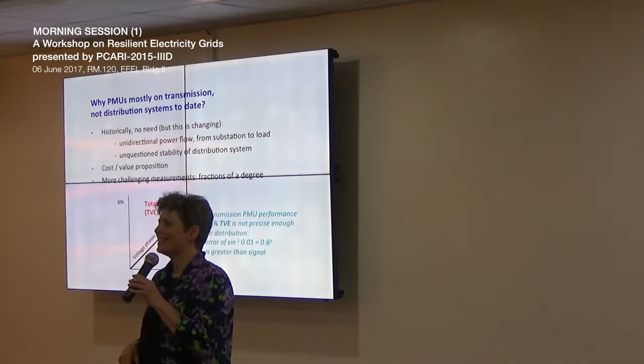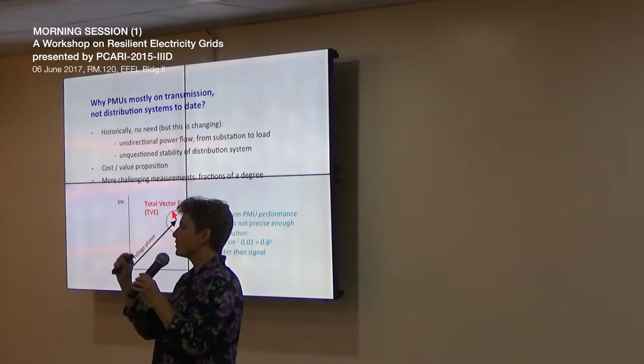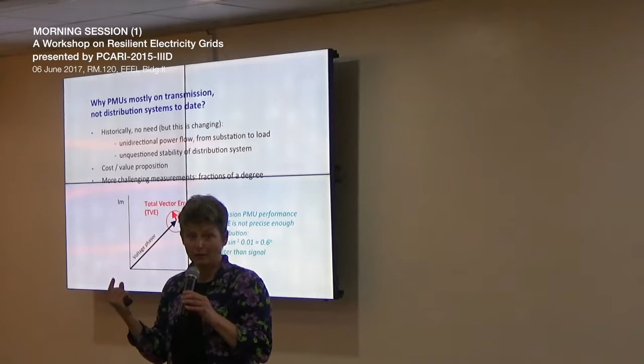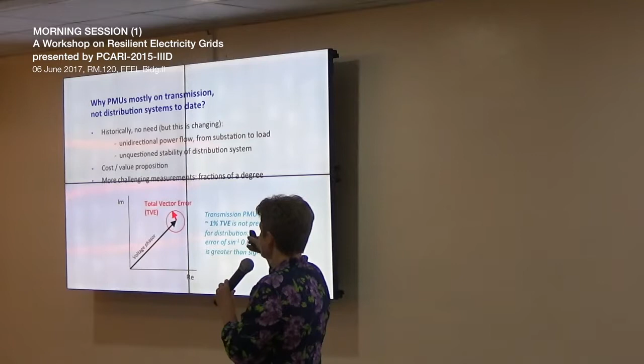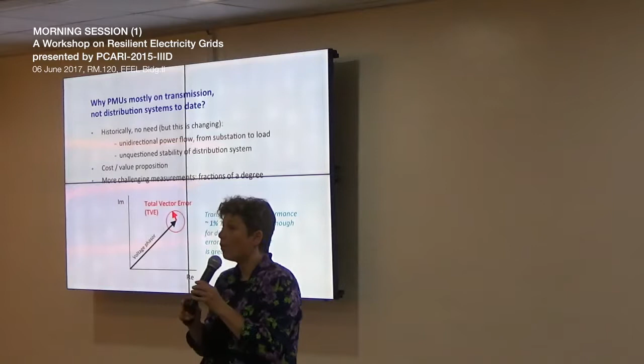Well, in distribution systems, 1% is not good enough. It's not going to tell you anything, because you're looking for differences between two nodes in the network that might be smaller than that amount of error. In fact, if you translate the 1% total vector error into a number of degrees, we get 0.6 degrees, and that may be bigger than your signal, which could be a small fraction of degrees.